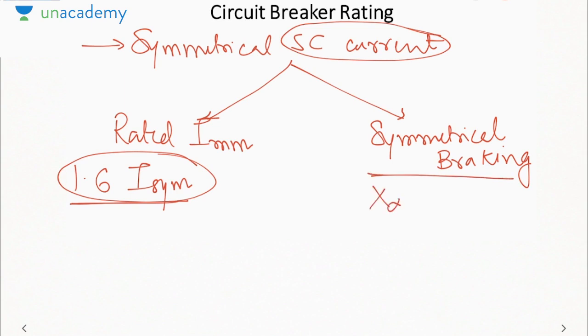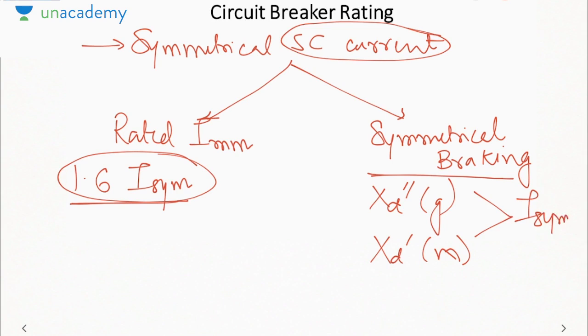Similarly, in case of symmetrical interrupting current or symmetrical breaking current, the first thing to be remembered is we will use XD double dash for generator and XD dash for motor, that is the subtransient reactance of a generator and the transient reactance of a motor. In case of a motor, since the supply is short circuited, it does not have any supply, so the motor will decelerate and it will enter the transient region faster as compared to a generator. So we will consider transient reactance of a motor and subtransient for a generator. Based on this, we will first calculate I symmetrical. Then we will multiply it by an empirical factor to account for the DC offset current.